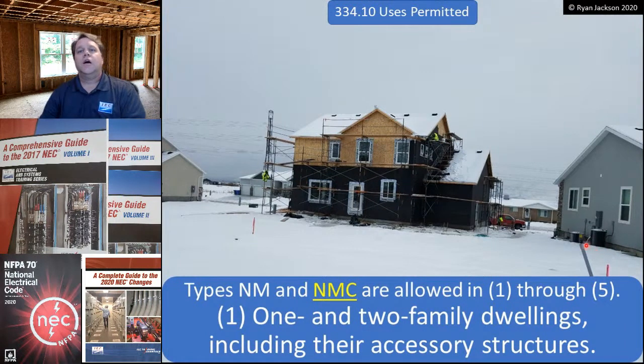Type NM and NMC are allowed as followed in 1 through 5. Number 1, one and two family dwellings, including their accessory structures. Cool. Wiring a house, doing a duplex, run NM cable. I don't care how big, how tall. Biggest house I ever inspected was 26,000 square feet. It was all NM cable. No problem there. I've inspected single family dwellings that were 4 stories. No problem there. Use it as big, tall, doesn't matter. And you can use it in their detached garages, accessory structures, without any special requirements. So that's the easy one.